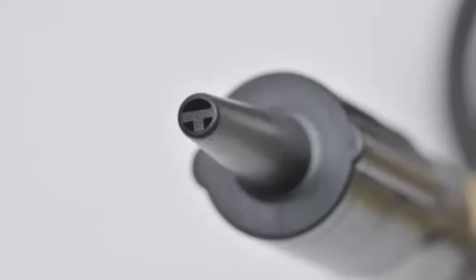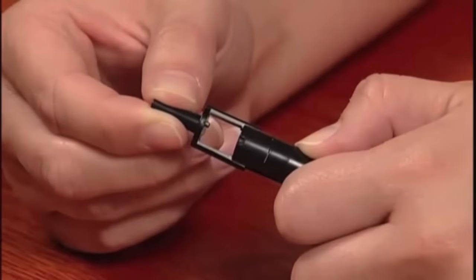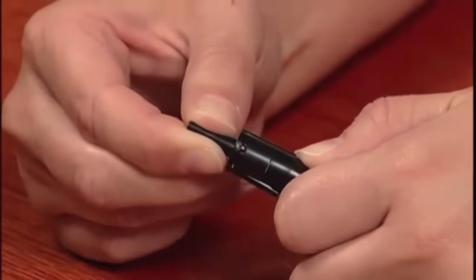If the condition persists, a different ear tip may be required to ensure a proper seal. It's also possible that the probe tip may be clogged and requires replacement. Earwax and other debris can clog the probe tip ports and cause the device to abort the test. This is easily fixed by simply replacing the probe tip.